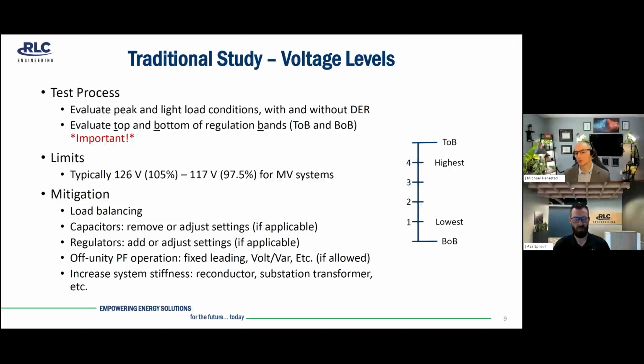There are other types of load flow settings occasionally included within software that allow you to specify the highest or lowest tap position within range. That will present usually a more conservative landing point for that tap position.